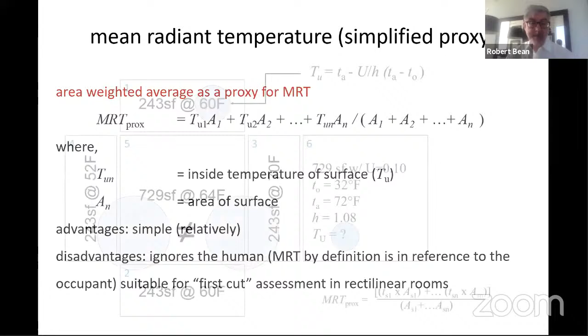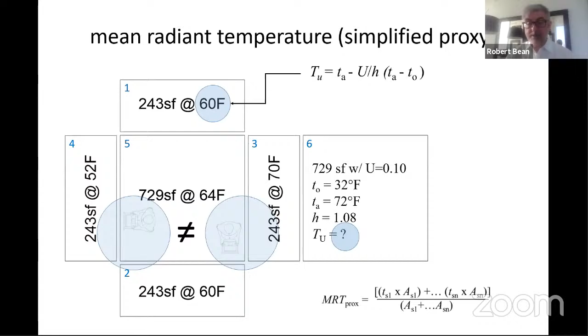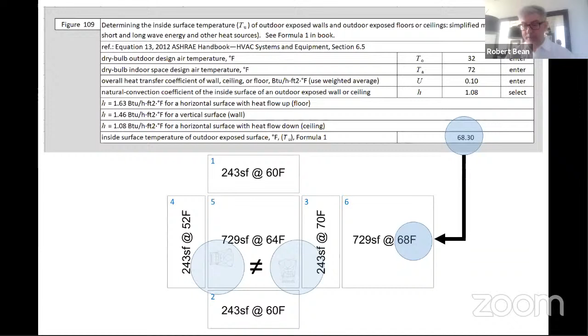So it is a weighted average and a very simple formula to do for each of the spaces. You just take the area times the temperature for each of them, and then put that into your weighted average. You can set that up in an Excel spreadsheet, and then you can do the calculation. So there we are in this particular space. We've put everything in, and then we've determined the surface temperature calculation for, let's say, the right-hand side quadrant of that ceiling, 729 square feet, so roughly 72 square meters, times 68 degrees Fahrenheit, which is roughly 19 or 20 degrees C. And we can do that for each of the surfaces and then come up with the mean radiant temperature. So in this case it is about 63.8 degrees Fahrenheit.